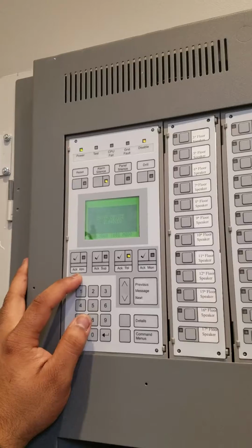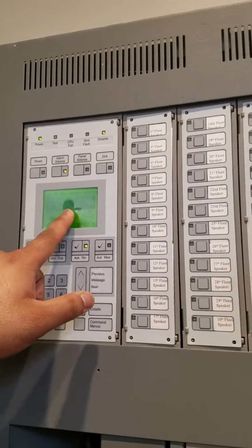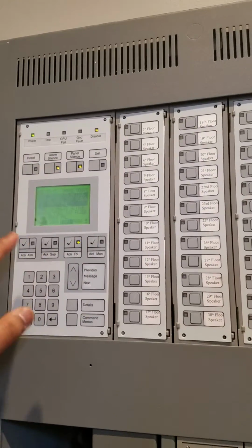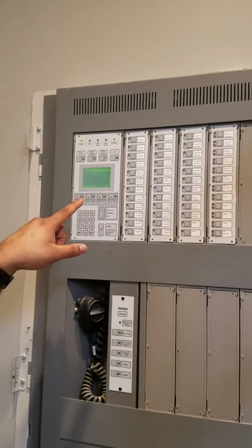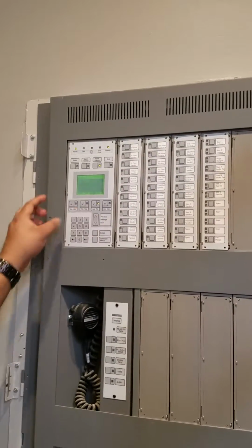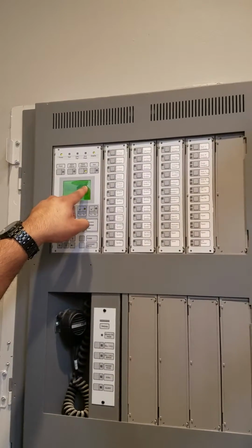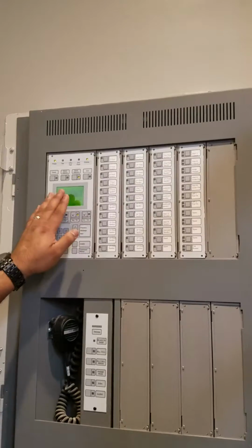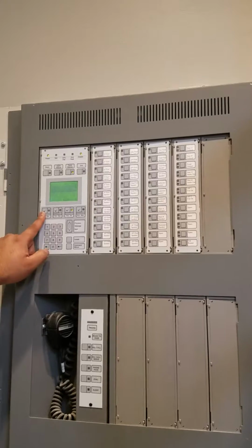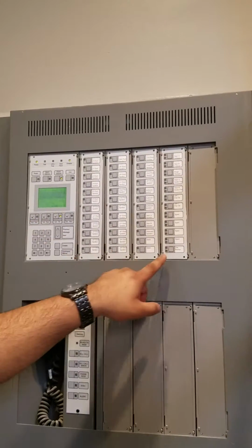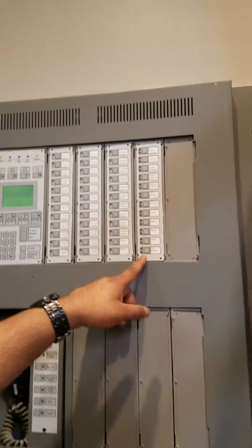You would see that alarm light now go out. And in your trouble category, that's where your pull station would be. So again, if you want to see more details of what you just did, you hit details, and it would tell you pull station, right? That was the pull station that was in alarm, and on the top here you can see disabled active, right? So you know that that device is disabled. With that, it would take your panel off of alarm now, right? And in this instance, if your fans are down, you will be able to hit fan restart to start your fans back up again, right?